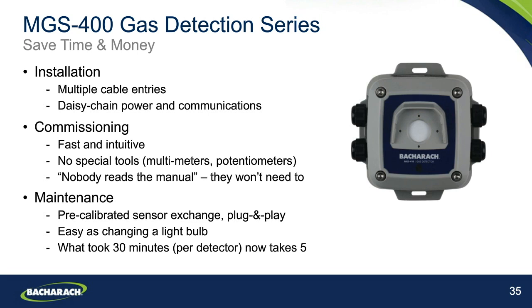Maintenance is also very, very simple. Pre-calibrated sensors are used here, and they can be exchanged in a plug-and-play manner within the detector. We can compare that to being as easy as changing a light bulb. And there's a lot of time saved here in that what would typically on this type of gas detector have used to take about 30 minutes to perform a full zero calibration and span calibration using certified calibration gas, which of course I must state is still possible with this system and runs on a semi-automated system with no manual adjustment, but a lot of time can be saved by using the pre-calibrated sensor exchange here, and that can be done comfortably in well under 5 minutes per detector. So there is a vast labour and time saving to be had here, which of course translates through into cost savings as well.